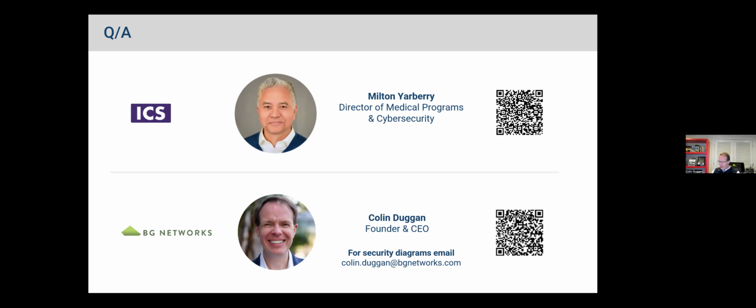Do you have any comments there, Milton? I mean, yeah. To the question, I thought the principles that we were using would apply to SAMD or software in a medical device as well as cloud-based. It didn't really matter the type of communication or where it was located. That's all part of your overview, if nothing else, and each communication link would undergo the same sort of process. So that was my initial thought. Okay, great.